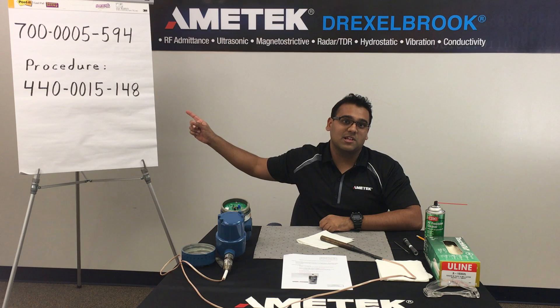Hi, this video is a cleaning procedure for the 700-0005-594 sensing element. This procedure is a supplement to the written instructions available on our website. This procedure may be required if you are experiencing false alarms. We found that over time debris can build up inside the sensing element and cause this condition.